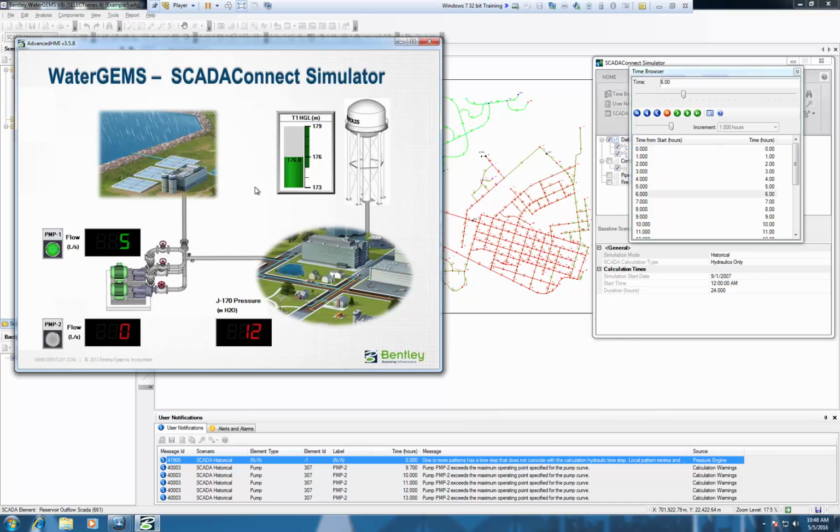So what's going to happen now is that as it's getting to the busy part of the day at 8 AM or whatever it is there, tank continues to drop, and then you'll see pump 2 is going to come on. So it gets to the secondary level where 2 pumps are required. A second control kicks in, pump 2 turns on. Once pump 2 turns on, the tank level starts to rise again.